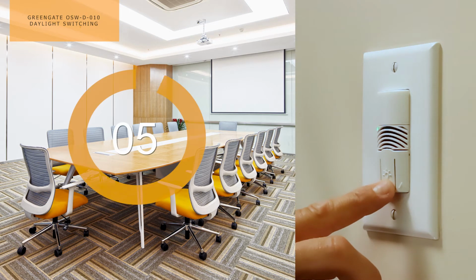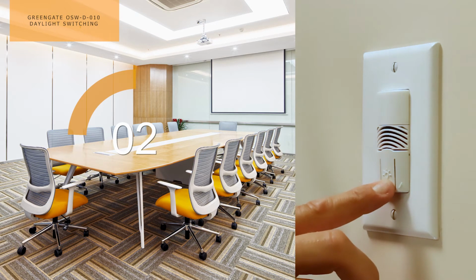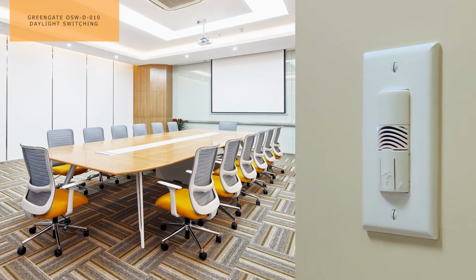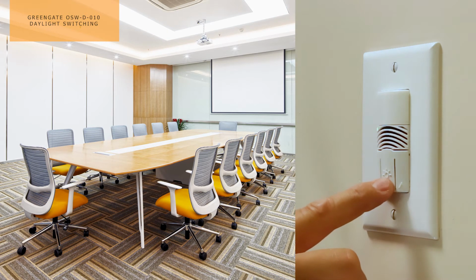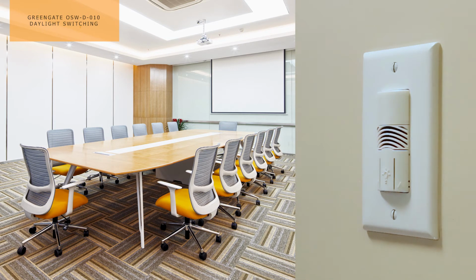Enter configuration mode. And then push the OnOff button 13 times. The LED will flash 13 times to confirm. Push the OnOff button 1 time to begin the calibration. The sensor LED will temporarily flash green. While the LED is flashing, move away from the sensor's view to avoid disturbing the calibration reading.